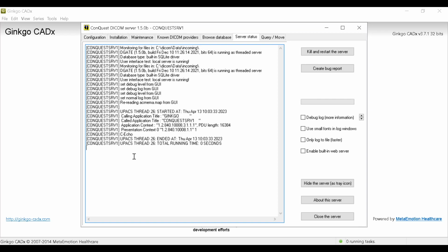The DICOM software is actually running as a software. It's layer 7. So there's a lot of things going on. It's more like, hey, check to see if I'm on your list. Make sure you understand my AE. Make sure you understand my IP. Make sure you understand my port, and then send me back a confirmation, please. That's a little bit more detailed, isn't it? So that's what we're doing here, and this is confirmation of that.